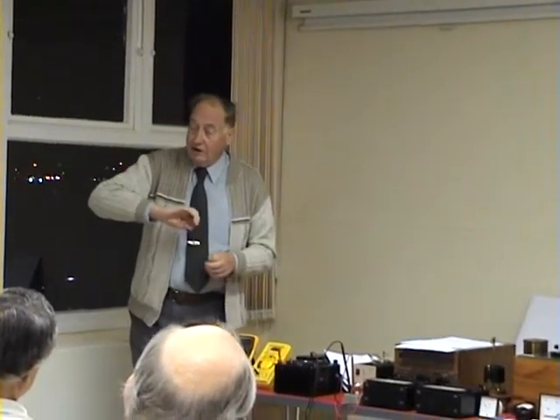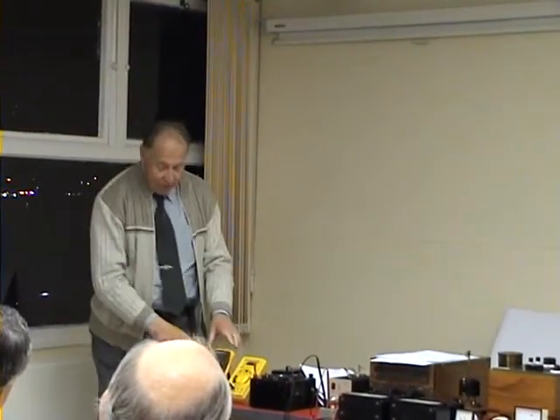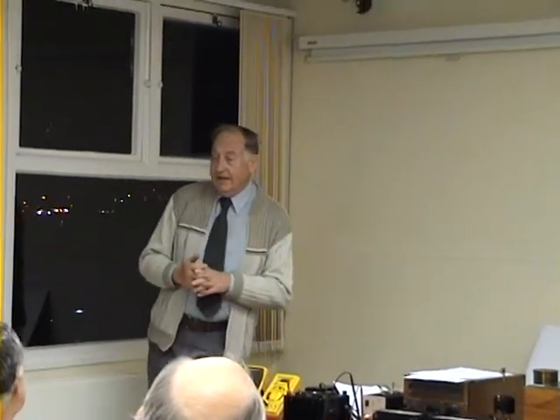Just check the current through it, and without thinking, he didn't change ranges. Well, he did change ranges by switching it to current. And he put this straight across the DC bus bar, across that shunt inside. Well, he brought the meter back, and it just sort of rattled. And when I took it apart, it was like a walnut inside, and that's all there was left of it.